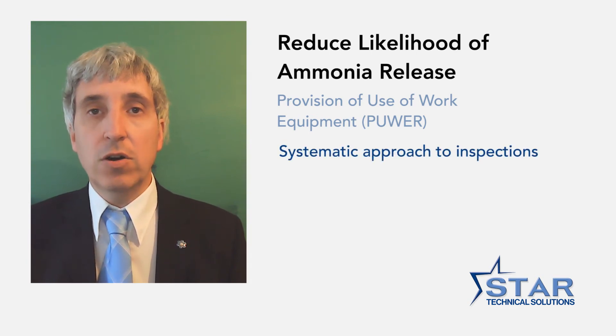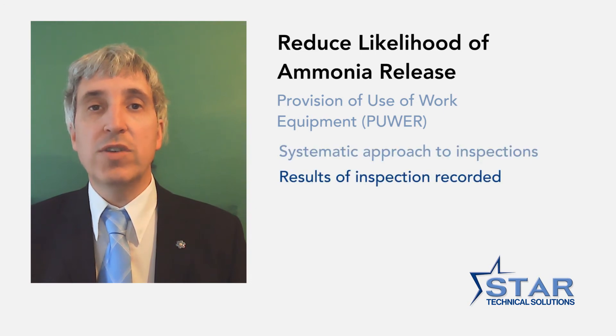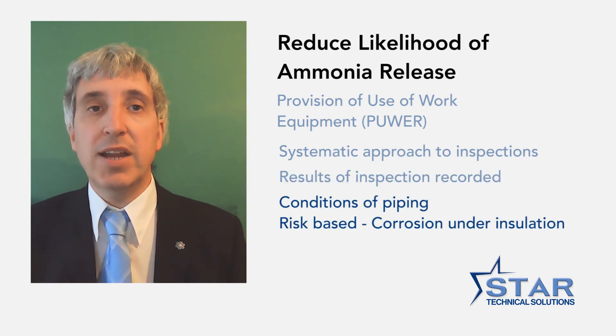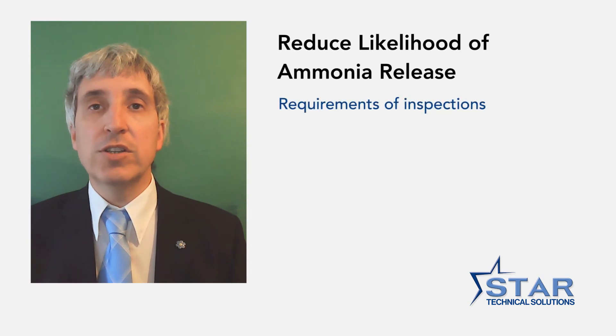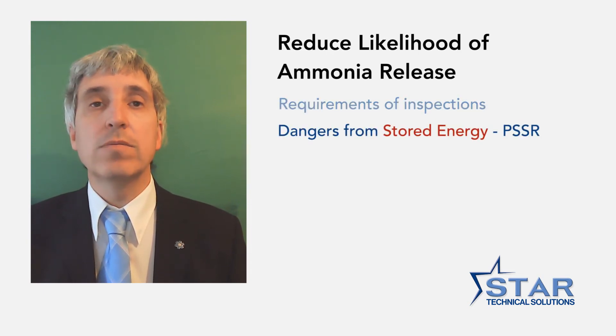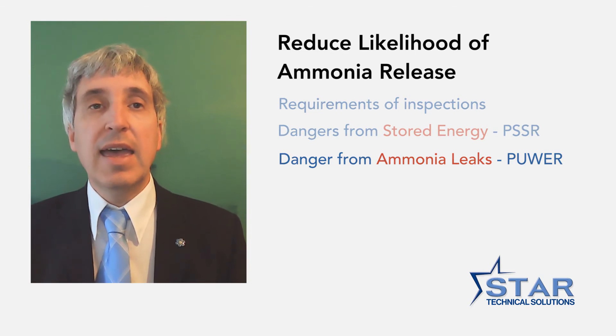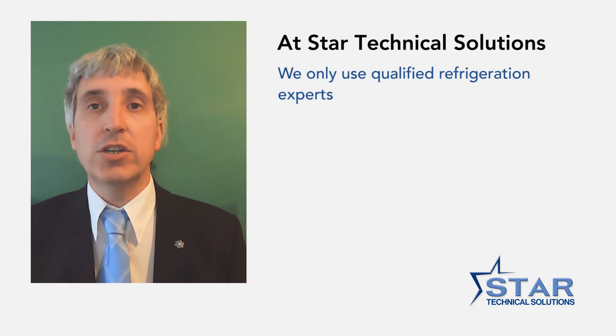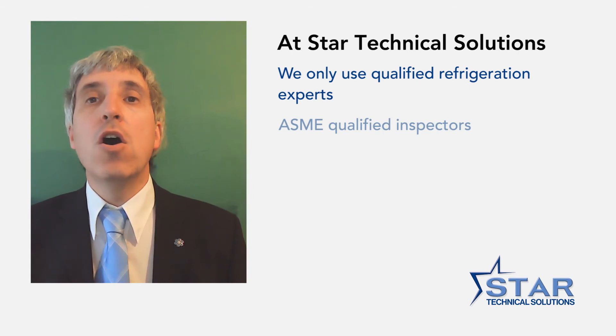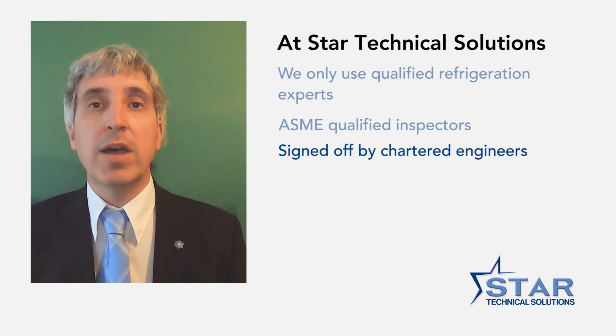As with the requirements of PSSR, PUWER also requires a systematic approach to inspections and the results of inspections must be recorded. These inspections should include the condition of pipework and have a risk-based inspection mechanism in place to assess the condition of corrosion under insulation. While some inspectorate bodies in the industry focus only on the dangers from stored energy as required by PSSR, they miss out on the most important requirement to carry out inspections of piping components to prevent the premature release of ammonia that results in further hazards, as required by PUWER. At STS, we only use qualified refrigeration engineers and designers who have ASME inspector qualification to examine your refrigeration systems. All our inspections are signed off by a chartered engineer as required by HSE guidance.